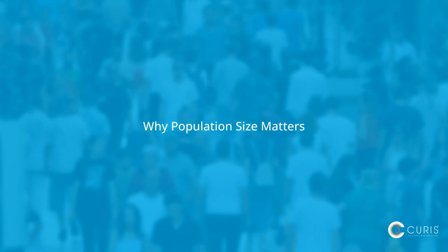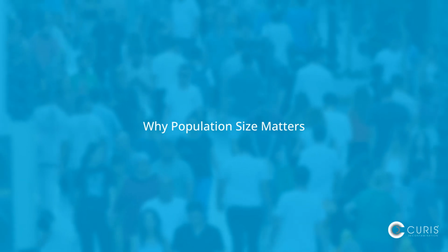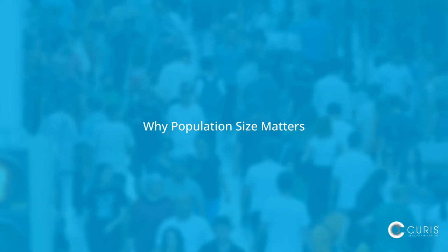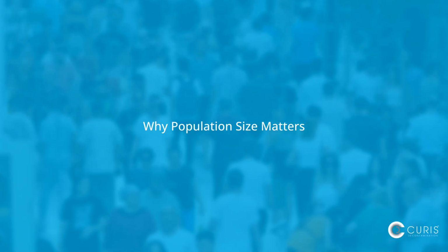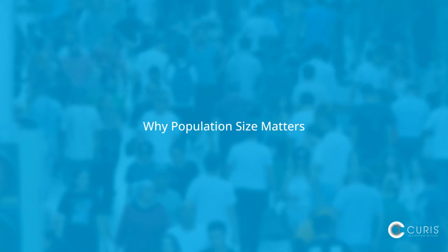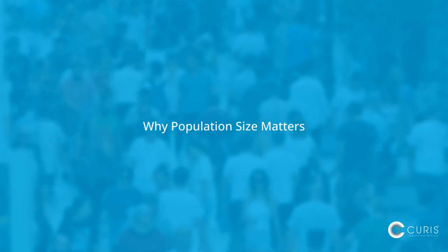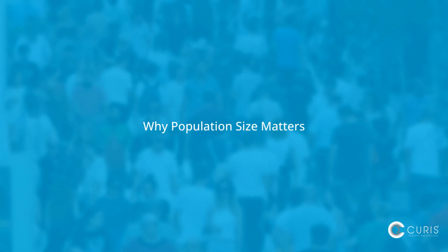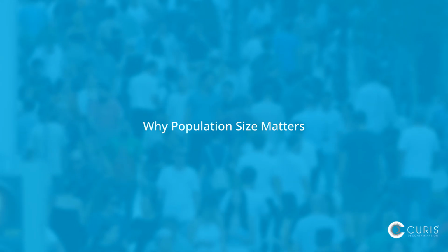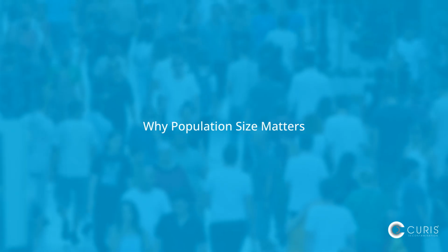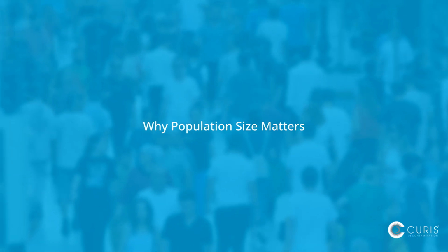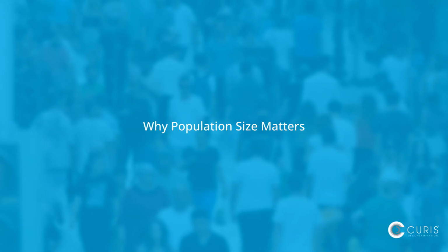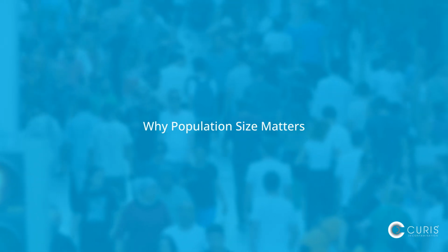It's not just the organism, it's also the number of microorganisms used in testing. Biological indicators often contain 1 million spores. Why so many? Because sterilization performance is measured using log reduction. A 6-log reduction, the industry benchmark, means reducing 1 million organisms to 1 or fewer survivors. This level of reduction defines true sporicidal efficacy.